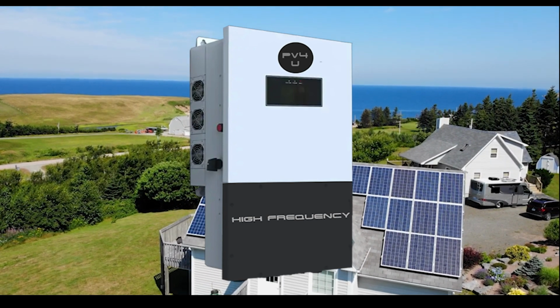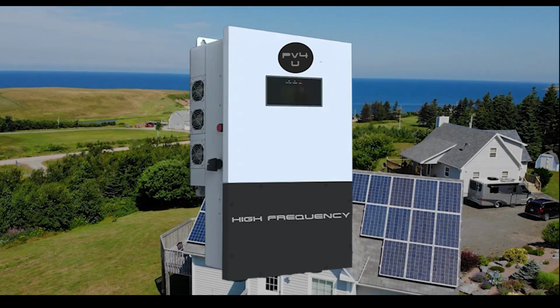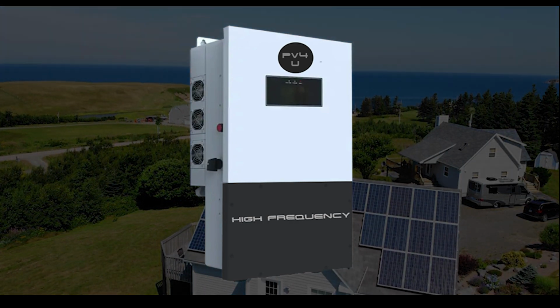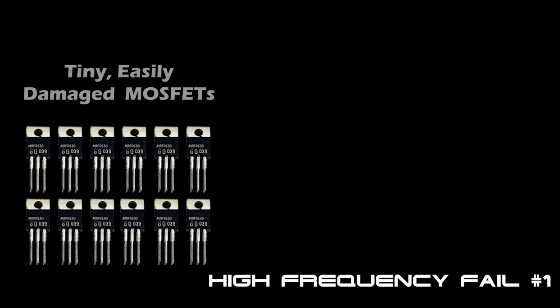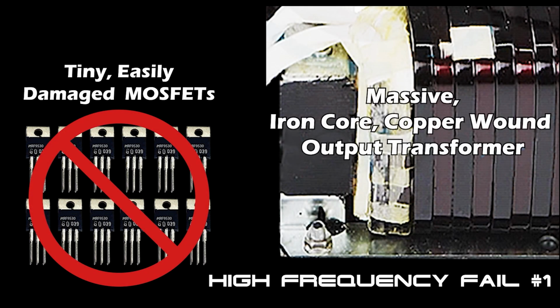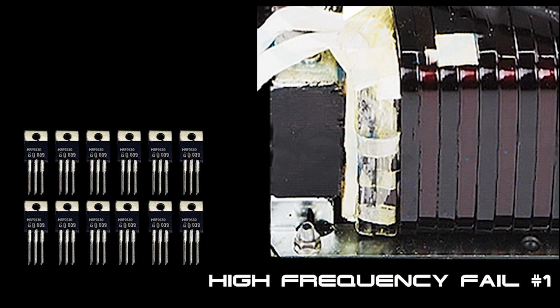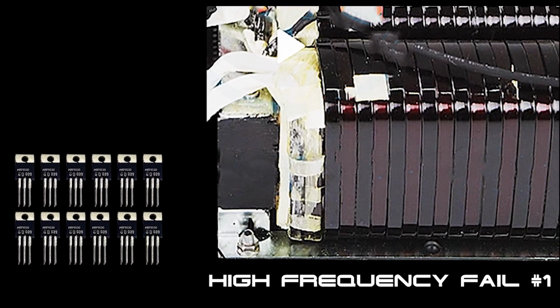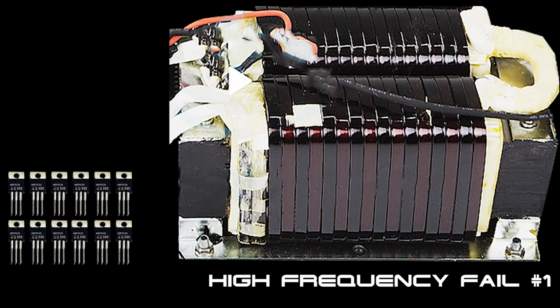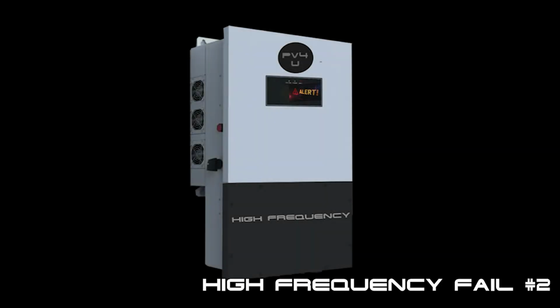we highly recommend that you do not watch this video, because you're not going to be happy with what you learn about the technology that's used in these inferior devices. In a high-frequency inverter, tiny, easily damaged MOSFETs directly power all of your loads. In a low-frequency inverter, on the other hand, all of your loads are powered by a massive, heavy-duty, iron core, copper-wound output transformer. This massive iron core transformer makes a huge difference when it comes to an inverter's life expectancy, surge capacity, and most importantly, its safety.